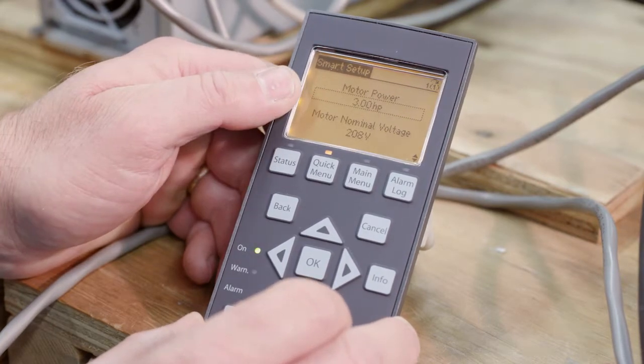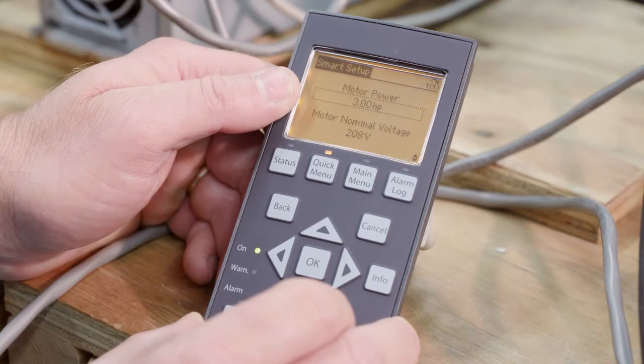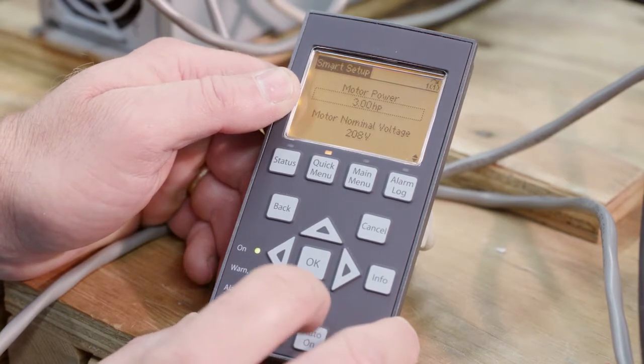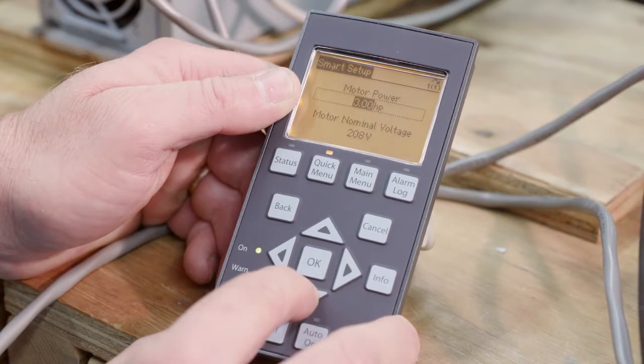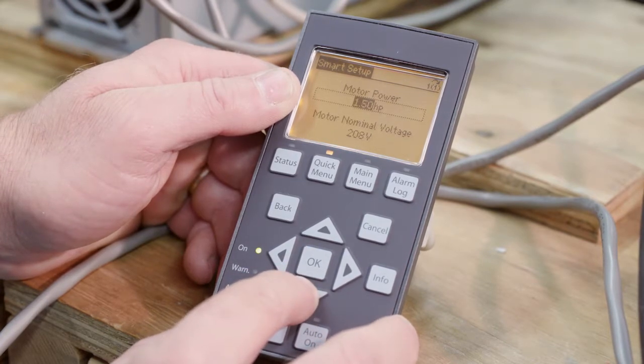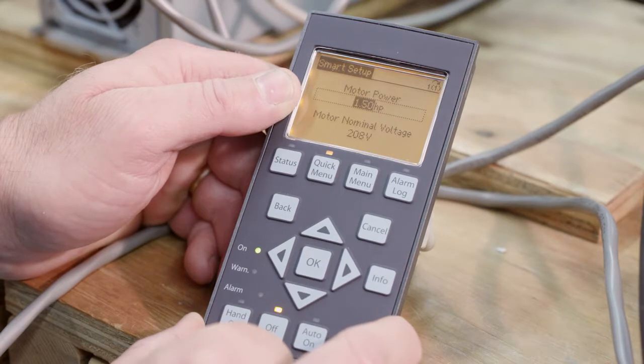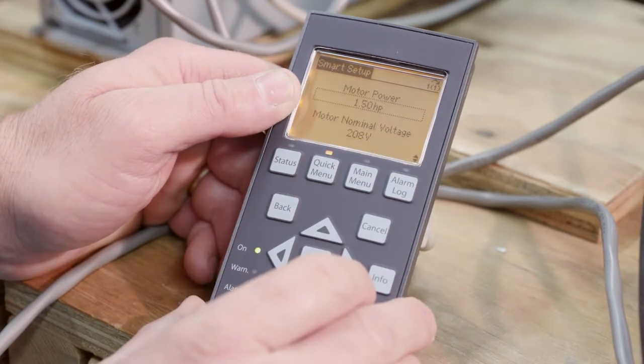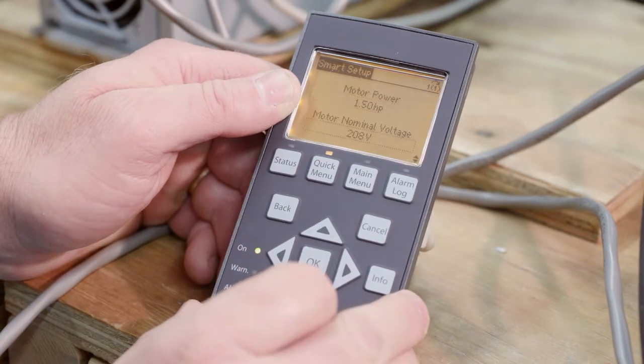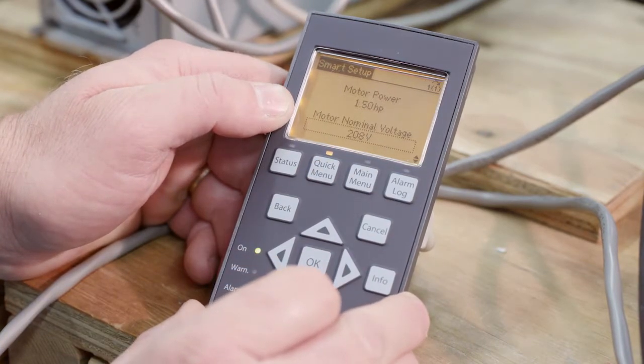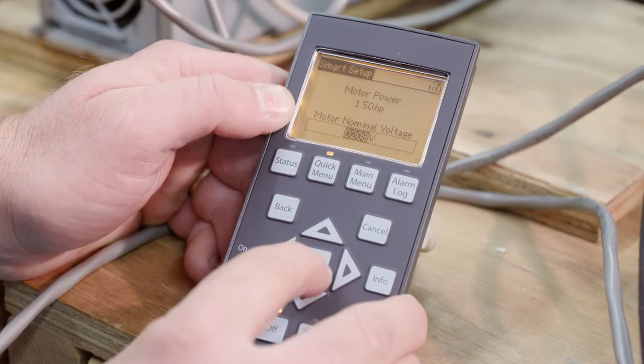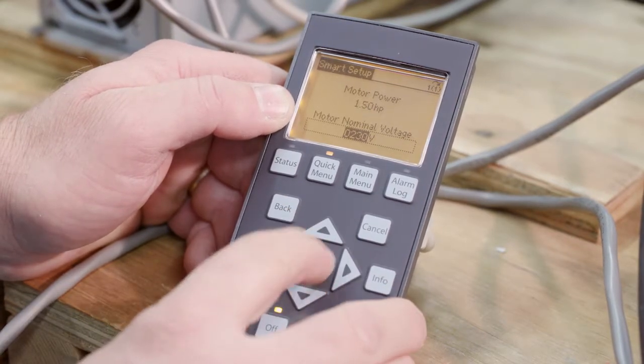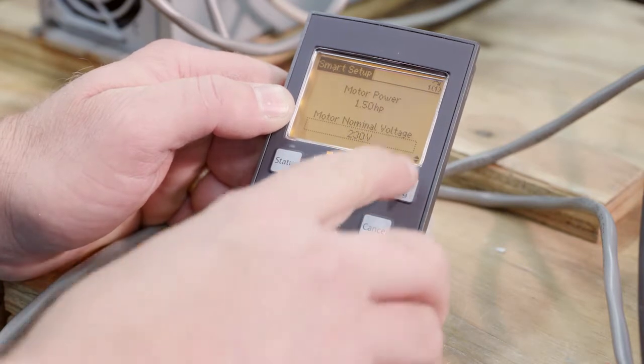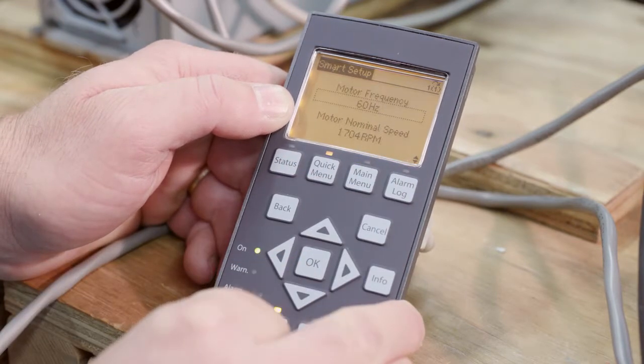That we can see on the motor nameplate. In this case, I've got a 1.5 horse motor, so I'm going to hit the down arrow to 1.5 horse and hit the OK. Again, it's given me this symbol on the lower right, which is saying it's okay to proceed. Nominal voltage needs to be 230. So see 220, 230, hit the OK button, hit the down arrow.